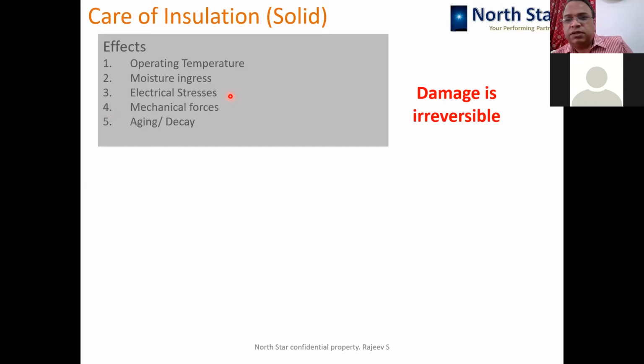When solid insulation is getting affected by moisture and all those parameters, the insulation strength is getting affected, and that insulation strength cannot be regained in any way. Of course, you can replace it, but that replacement is not as easy as liquid insulation, that is oil. So when we are talking about solid insulation, we must be very, very careful that our action should not lead to the deterioration, or unwantedly fast deterioration, of the insulation quality.